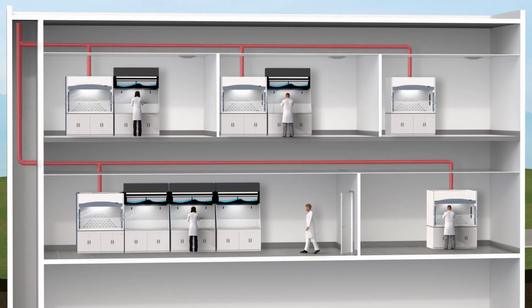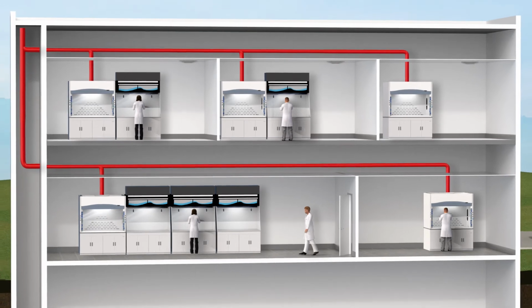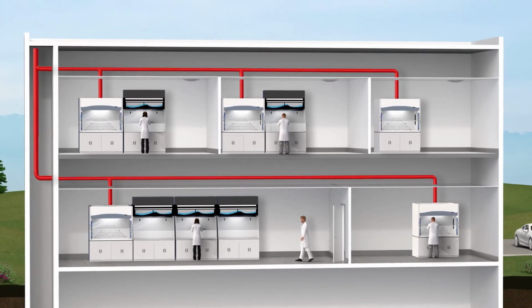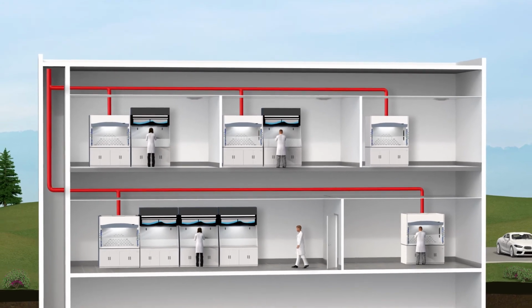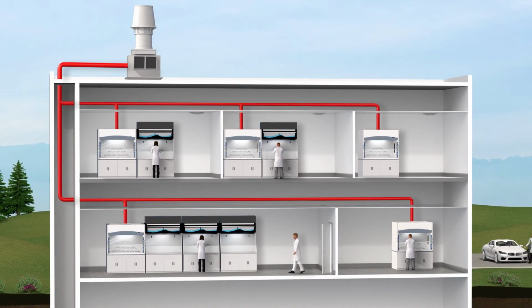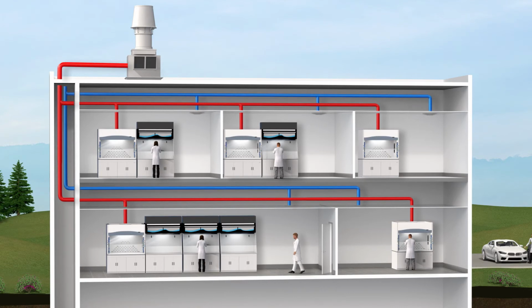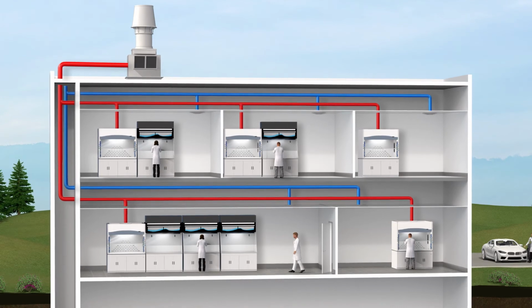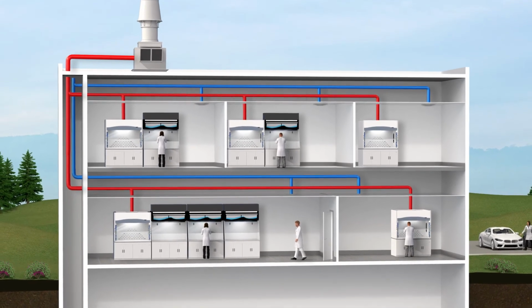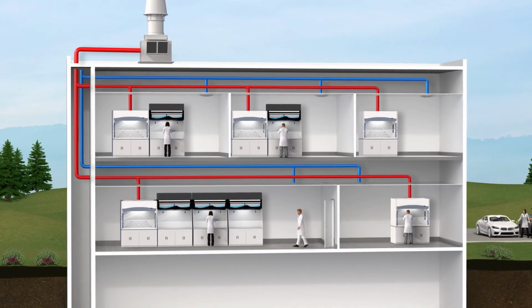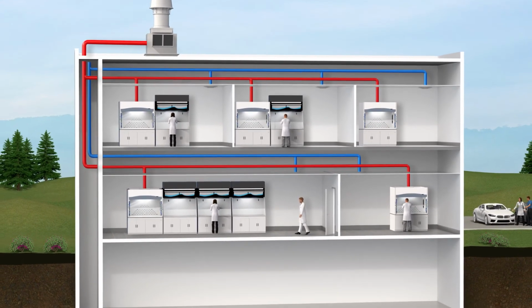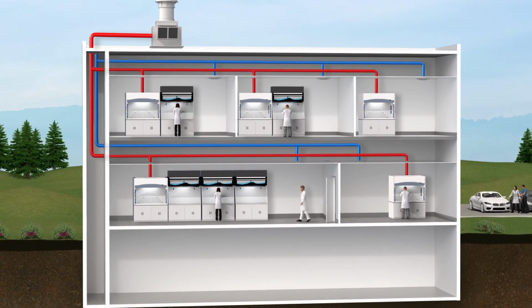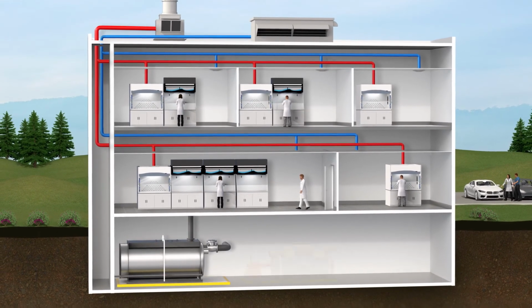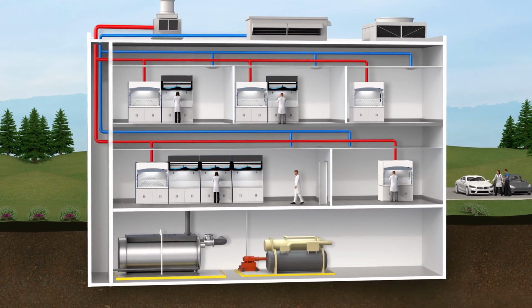Exhaust ducts will be smaller by reducing the lab's total exhaust air down to the code-required ventilation rate. Exhaust fans are then fewer and smaller, and the supply air ducts will be smaller too, due to less air being exhausted from the building to begin with. Airflow controls are simplified, if not eliminated, and much less costly. Air handling units, boilers, chillers, and cooling towers are all smaller.